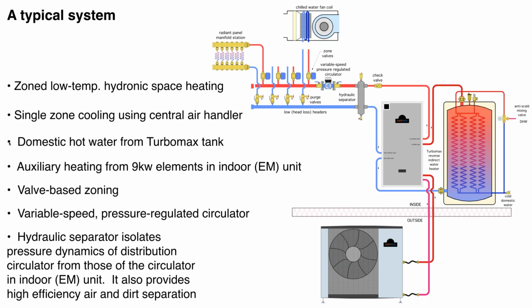This is really the type of system that the Enertech unit was originally conceived around, where we have the outdoor unit, we have a piping set that comes into the indoor unit. And again, this is not refrigerant piping. All the refrigerant is factory charged and sealed in the outdoor unit. So we have piping with an antifreeze solution that comes into the indoor unit, and the controls and the hardware necessary to route that energy to several different loads is contained within this indoor unit.